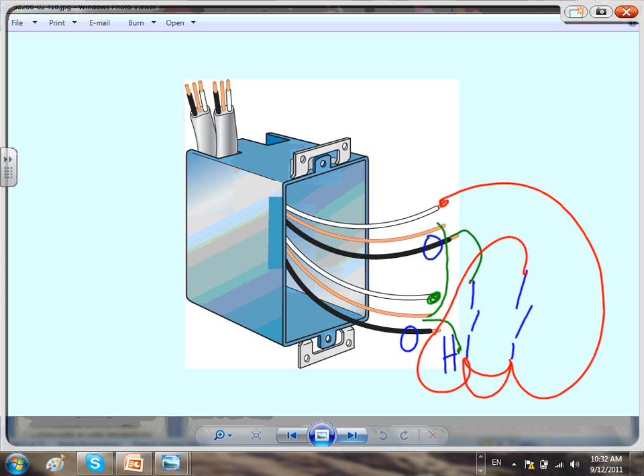Long story short, guys, because of that requirement, you will now be required to use a 4-conductor cable in a lot of applications. We used to get away with 2-conductor and 3-conductor cable, but for some 4-way and 3-way switch applications, you might have to use a 4-conductor Romex cable. Be aware of that.